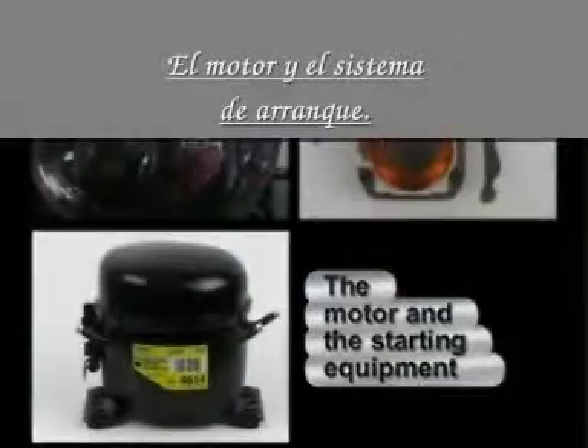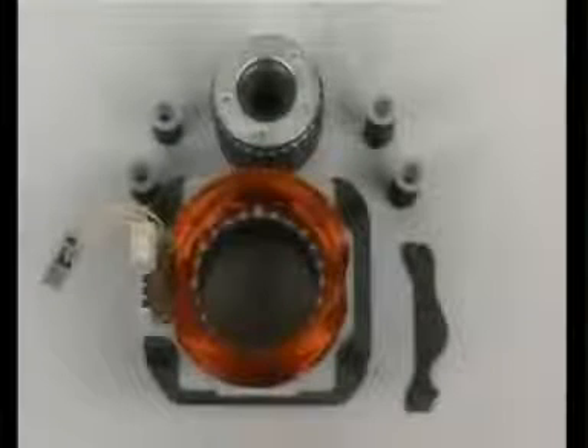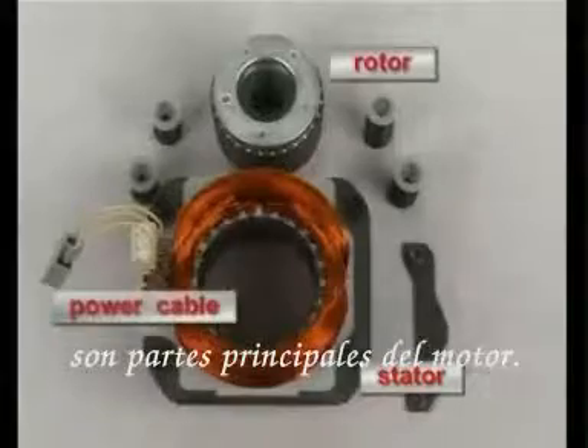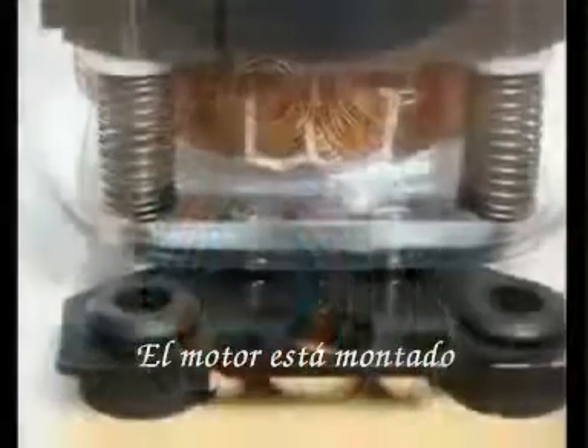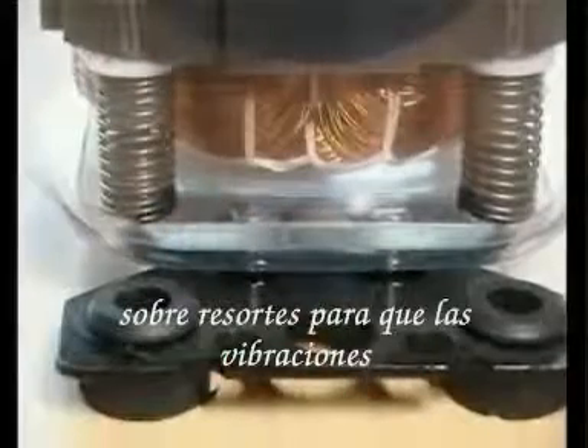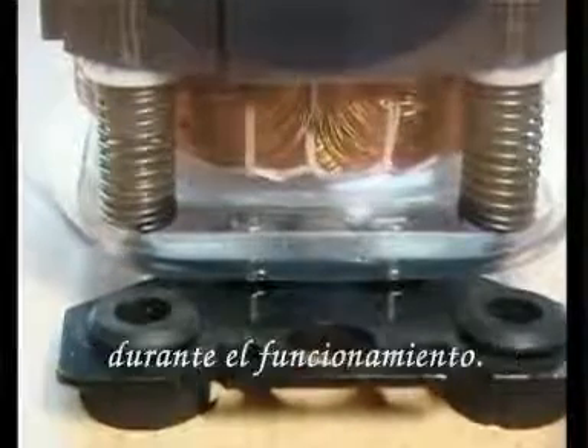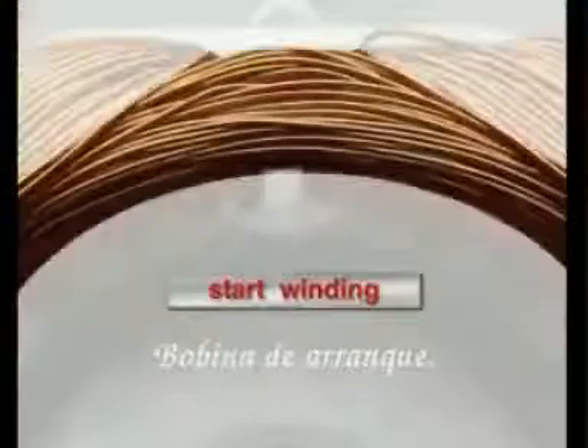The motor and the starting equipment: the stator, the rotor, and the power cable are the main parts of the motor. The motor is mounted onto springs so that vibrations are not transferred to the compressor shell, ensuring a low noise level during operation. The stator consists of a stator stack which is welded together out of sheet metals and two windings of enameled copper wires — a start winding and a main winding.